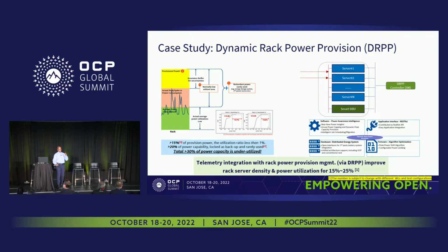And so you can operate in that red zone, you can also put in a battery-backed unit on a per-rack basis to cover those peaks. Then you can improve your rack utilization because you can pack more into your rack. And also, you're not wasting power. The power that you put in is really used power, not power that you're wasting.